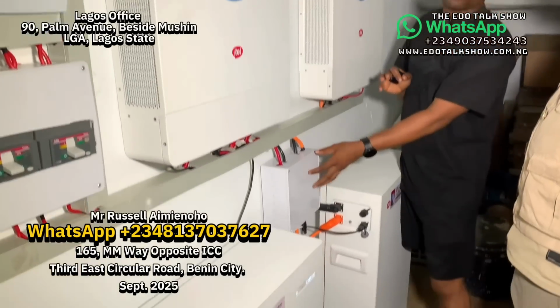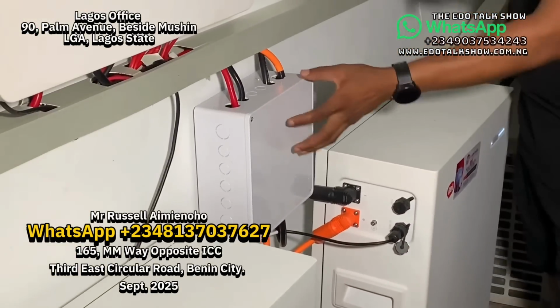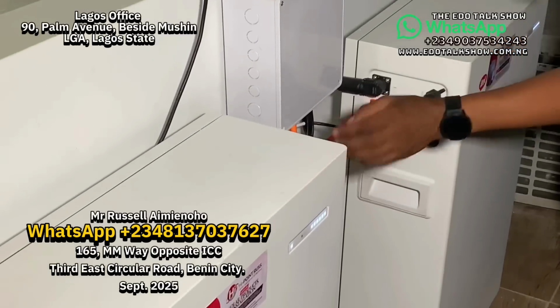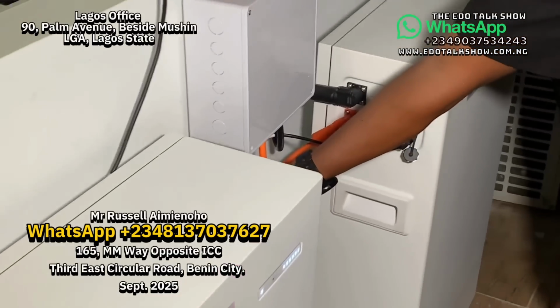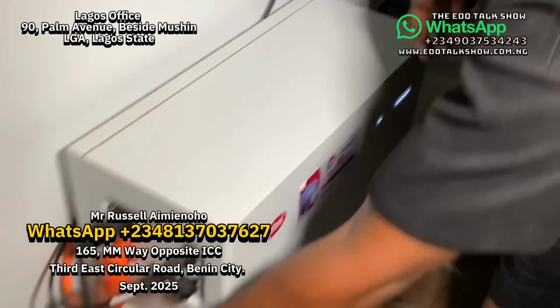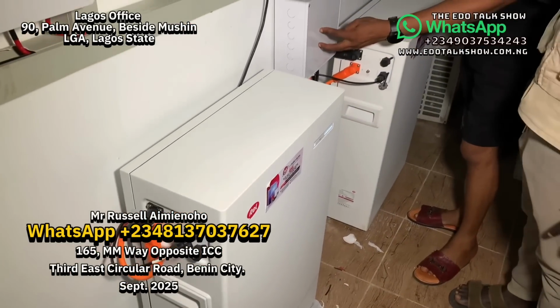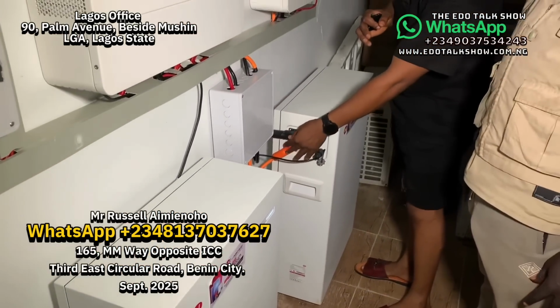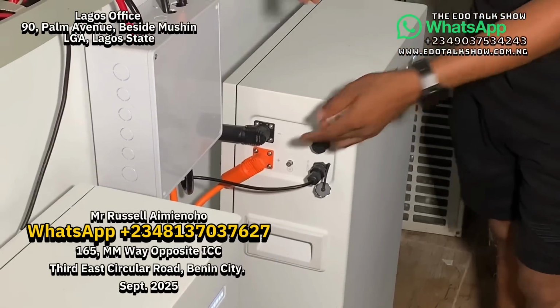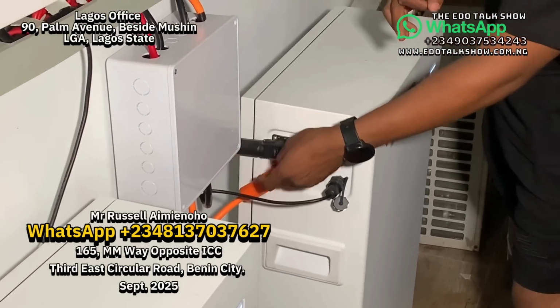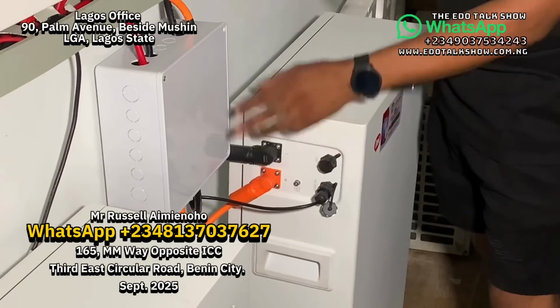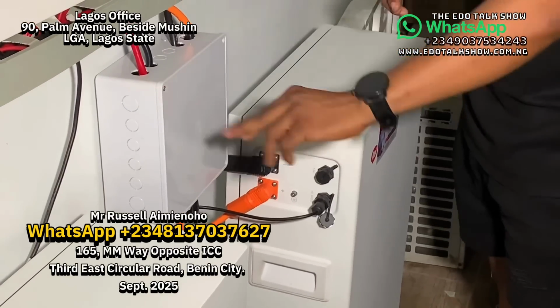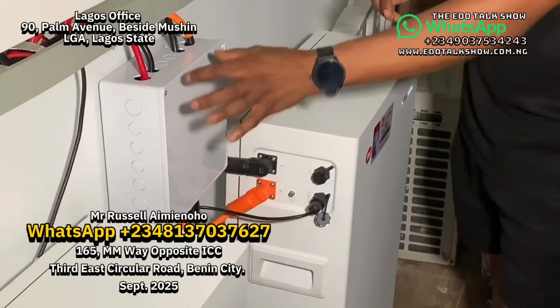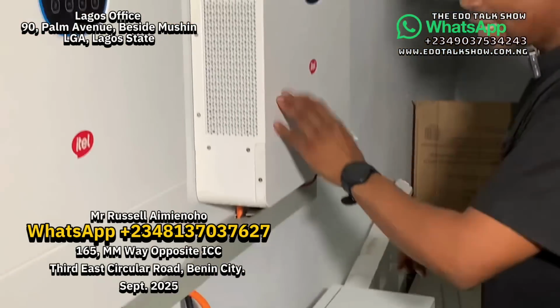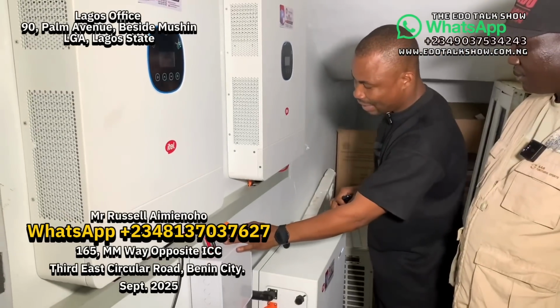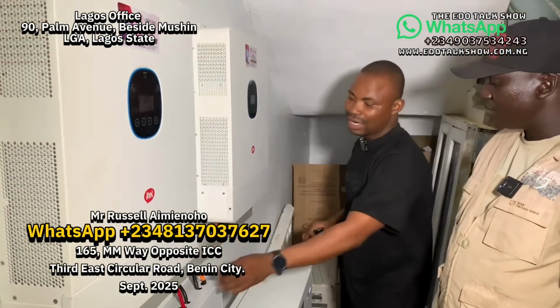Here we call the battery bus bar. Inside this bus bar, on this lithium battery, you see the black and red wire, that's the positive and negative. When we pick from here, you enter inside this bus bar. The positive and negative, the black and red, we connect them together. We join the red ones, and we put them on the same bus bar line. Then the black ones, we put them on the same bus bar line. And from there, we can feed each inverter. If you look here, the red and black feed this inverter. Red and black, they feed the inverter.